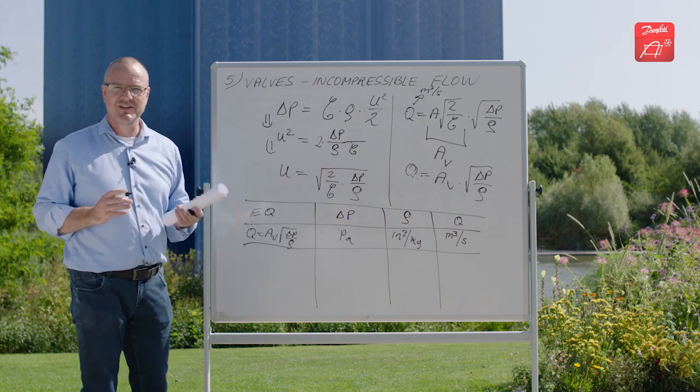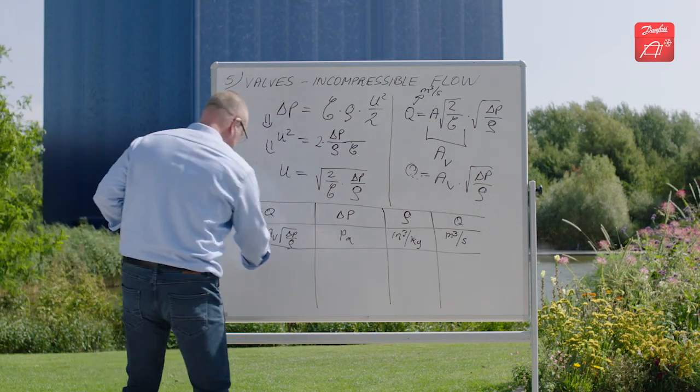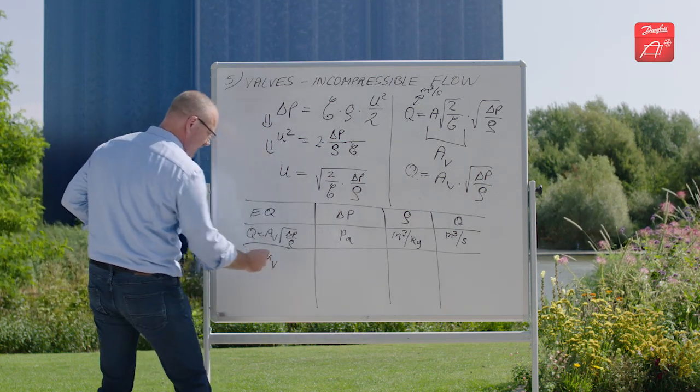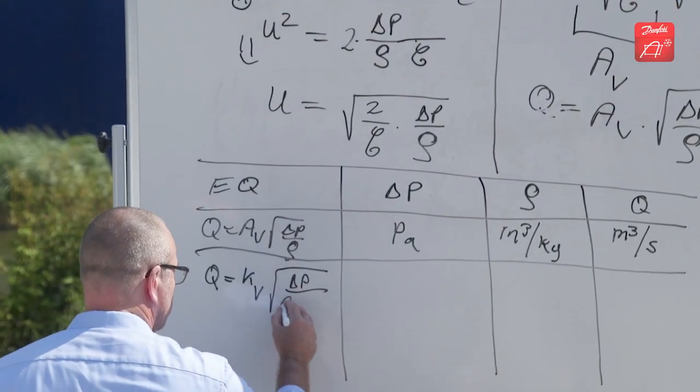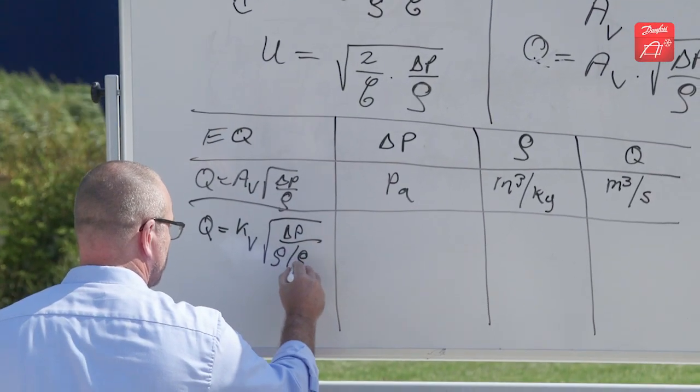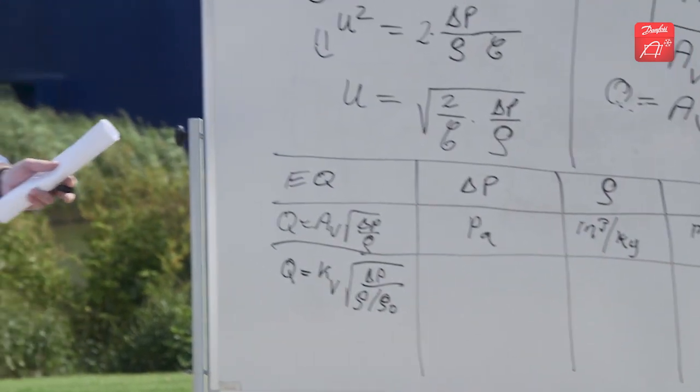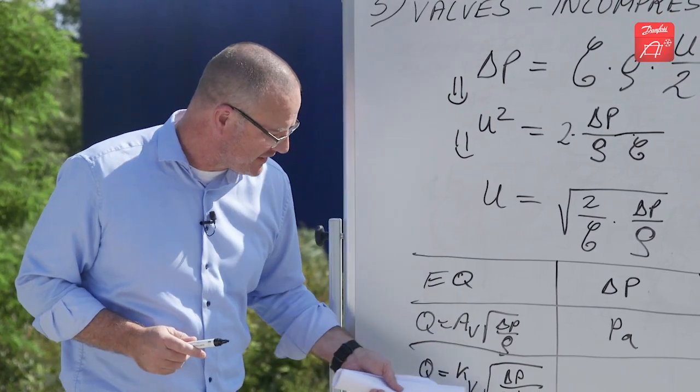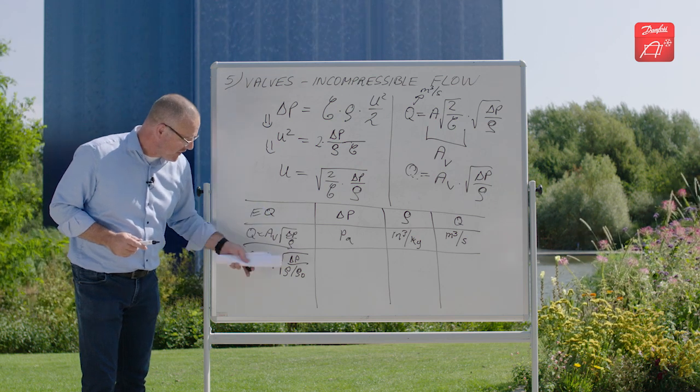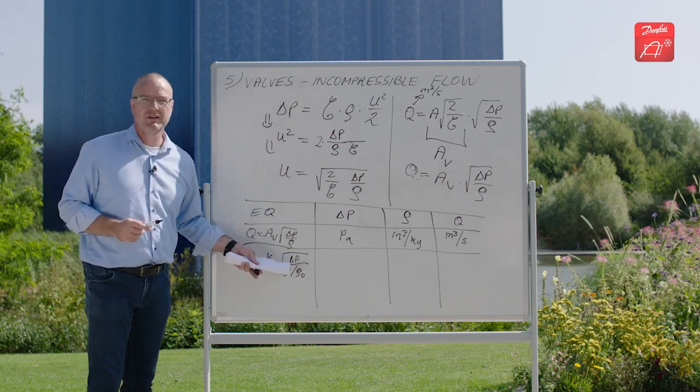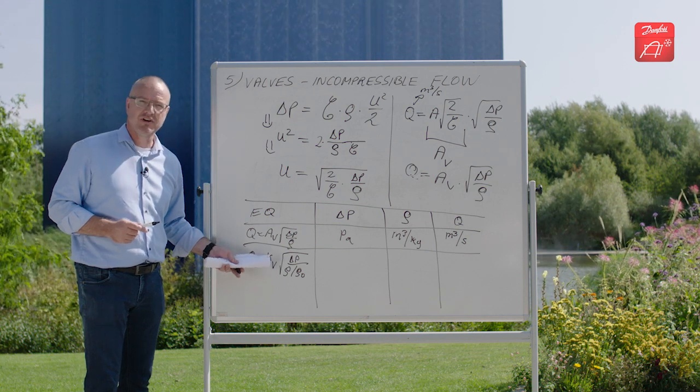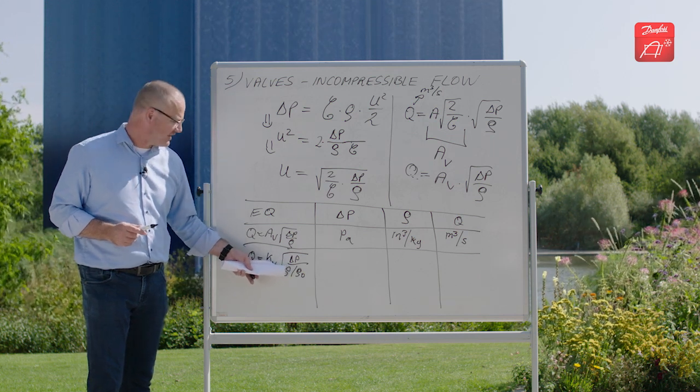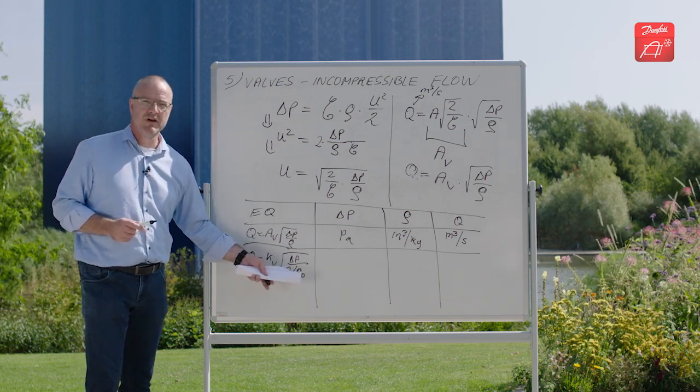Then you have the equation if you use the normal international units, where you call the flow coefficient KV. Now for tradition: because these equations were evolved in the 19th century, you used water all the time. When you did measurements of KV values of valves, you did it on water, then you took the density of the fluid you were going to use and divided it by the density of water where you measured.